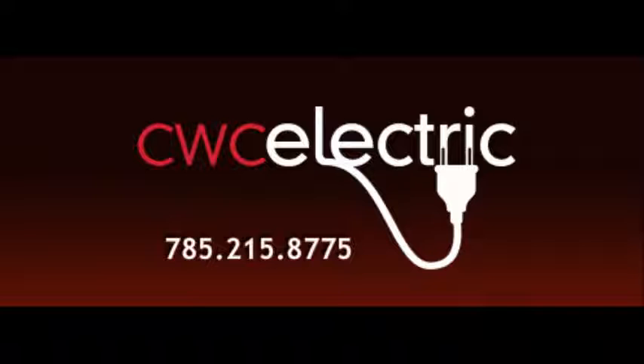There are several generations of GFI outlets. The older ones, when they quit providing GFI protection, the outlet would keep working, so you wouldn't know you'd lost the protection—you probably see that called out a lot in real estate inspections. Then came the next generation, required to be manufactured so that once GFI protection quits working, the whole outlet quits working. That's a good sign—it just needs to be replaced, and if someone's handy with tools, they can turn off the power and change it out themselves.